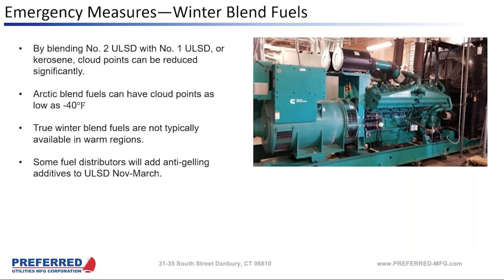And another thing to keep in mind too, if you're waiting in line to get fuel in a situation where maybe you don't have a 72-hour outage, but you have a short outage or limited delivery schedule, you may be waiting in line for a winter blend, where if you have a system that can take something standard, it might open up some options in an emergency situation.